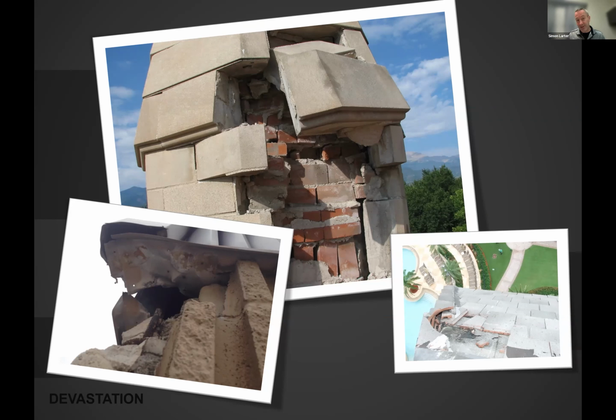I've seen this happen on high rises, where chunks of concrete fall a couple hundred meters to the ground below. I've seen it happen on chimneys, even roof tiles, terracotta tiles. They don't have a whole lot of water in them, but lightning will still do damage. That's the kind of damage lightning does to concrete. Reinforced concrete, lightning will flash through it to get to the reinforcement bars. If they're discontinuous, you could have flashovers within the concrete that start to compromise the structural rigidity of that column. So either way, it's probably better to have a lightning protection system so you're not letting incidental parts of your building carry the current to ground.